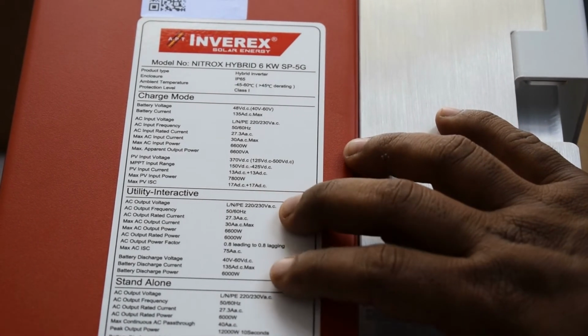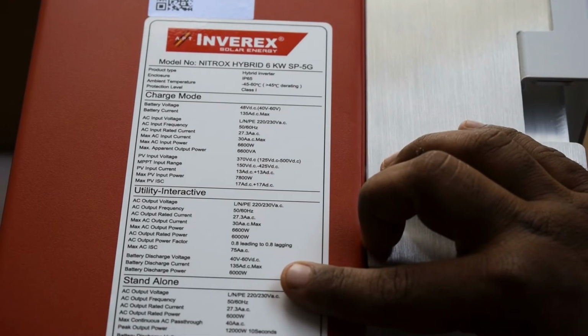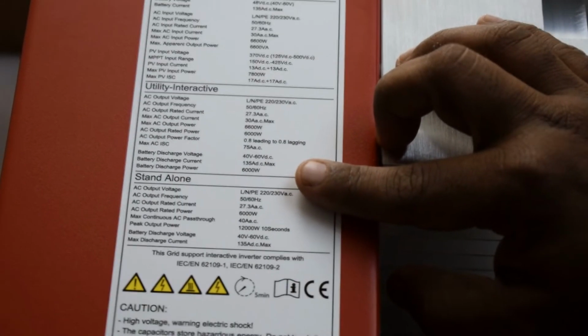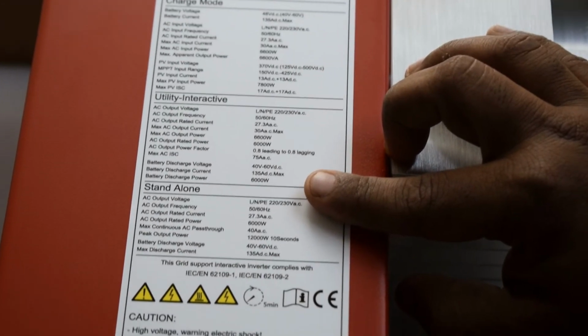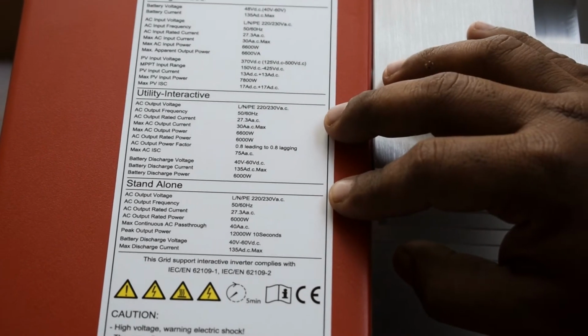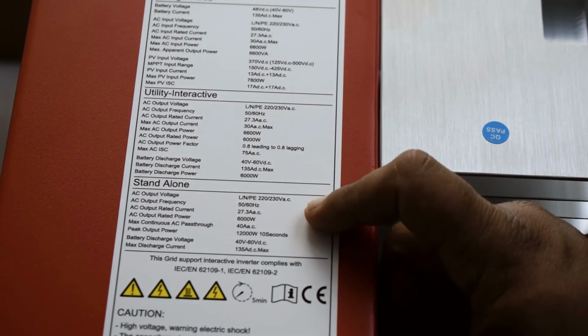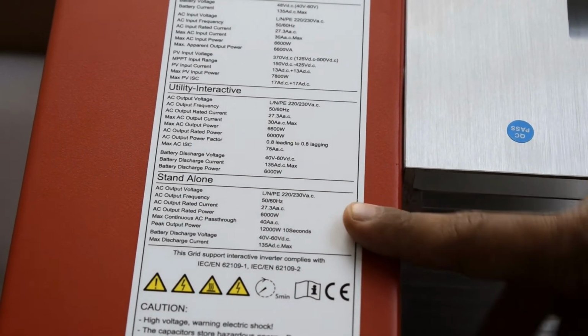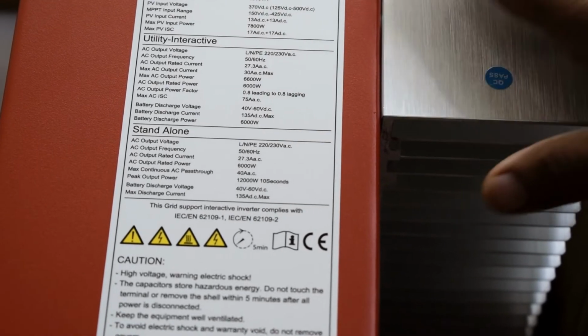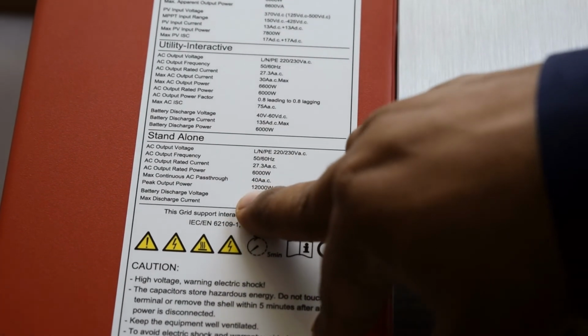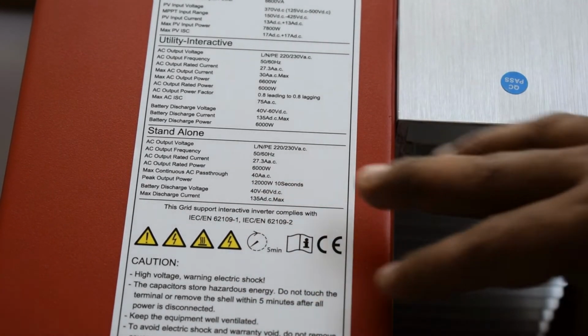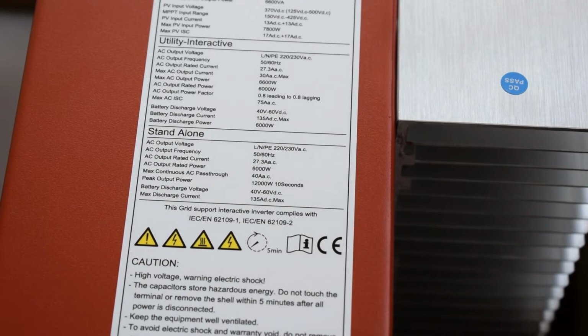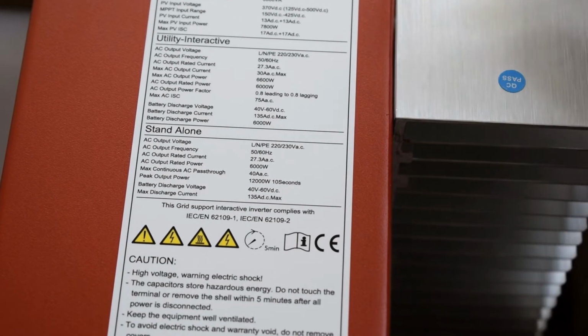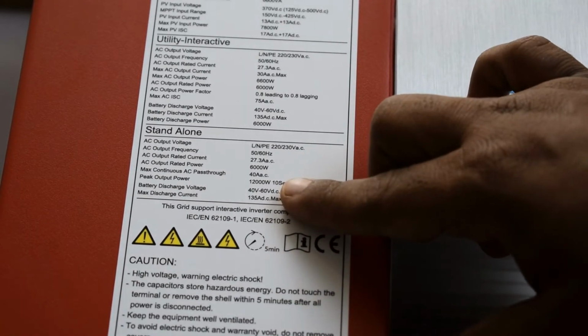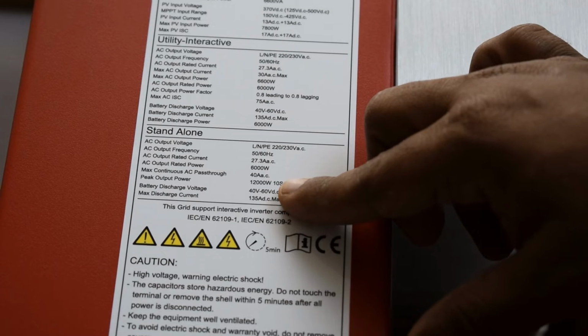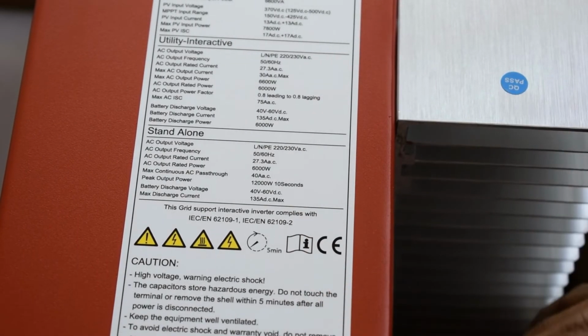Okay, so for utility line interactive we have the same specs: 6.6 kVA, maximum power 6000 watt, and the battery discharge power is around 6000 watt, again 6 kilowatt. For standalone, it means it is not taking power from solar or battery, it is taking from the grid. For the grid we can connect this inverter up to 12 kilowatt for 10 seconds only. So we can connect only 6000 watt, but for any surge power for starting a high motor or ACs, it has a starting torque, so it can take up to double the power of the inverter for 10 seconds. So these are the specs.